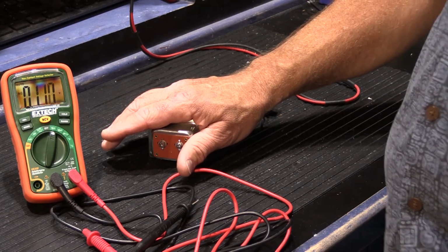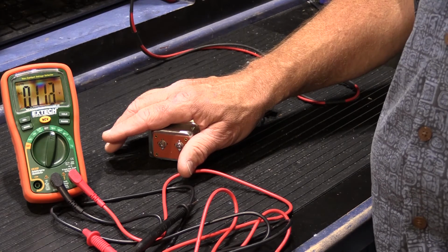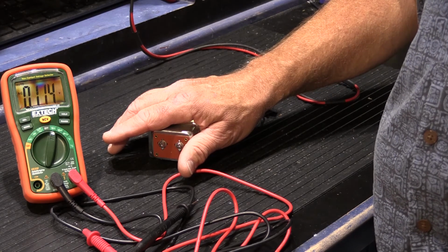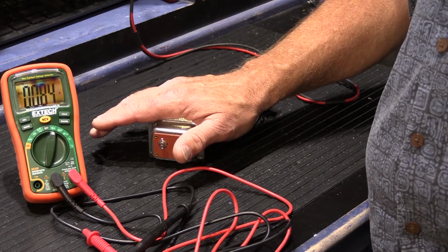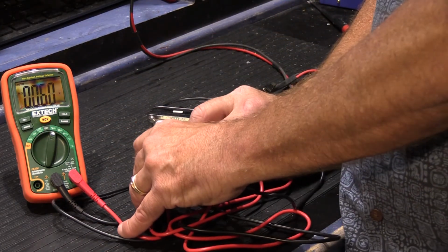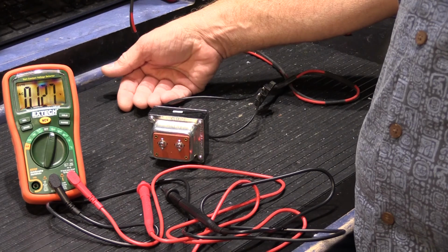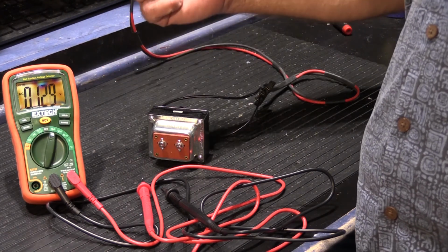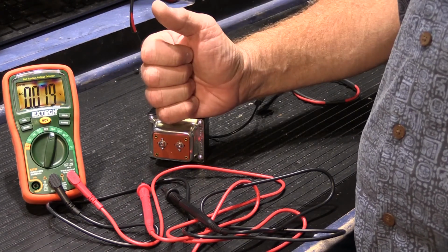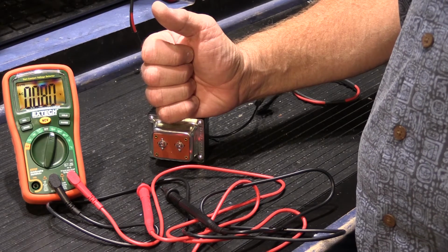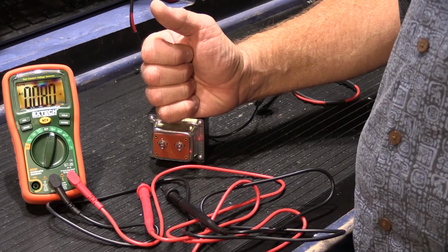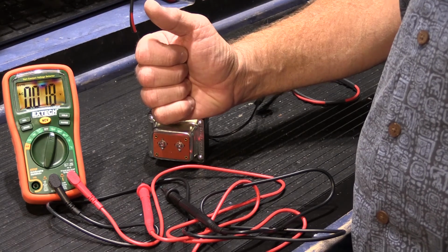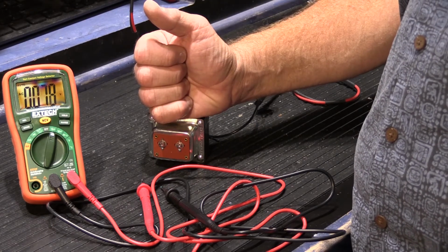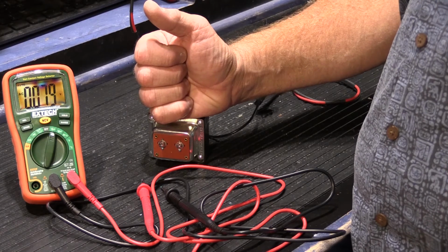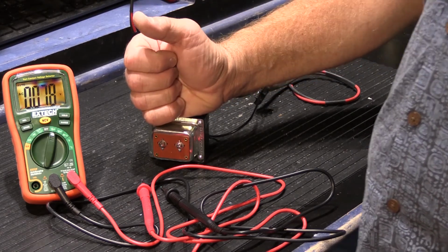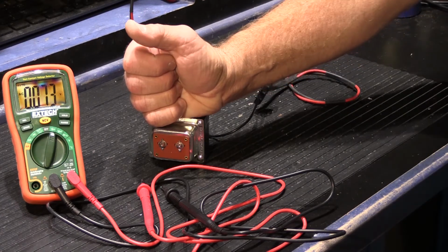If we go back to that severely old, 35-year-old failing NuTone intercom system causing the transformer to get really hot, when you measure the voltage here with your probes you might measure 9 volts. That's because the device is demanding so much power the transformer can't keep up, so the voltage drops and drops. Plus it's probably burning hot, and hot transformers are less efficient, which makes the voltage drop too. So a free running transformer will always read higher than what's specified.